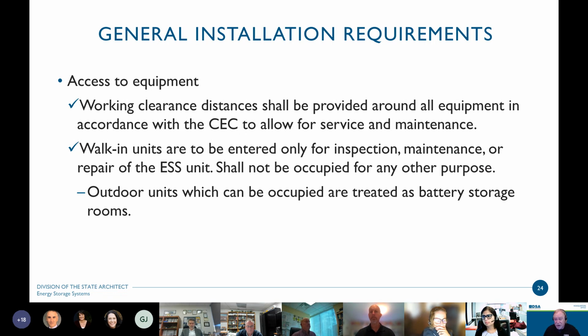Walk-in units, remember we're talking about pre-engineered, pre-manufactured ISO type shipping container units, are to be entered only for inspection or maintenance. They're not to be occupied for any other purpose. So somebody shouldn't be putting an office in there or something along those lines. For outdoor units, which can be occupied, then they're going to be treated as a battery storage room. And then, of course, all of the additional requirements for battery storage rooms are going to have to come into play.